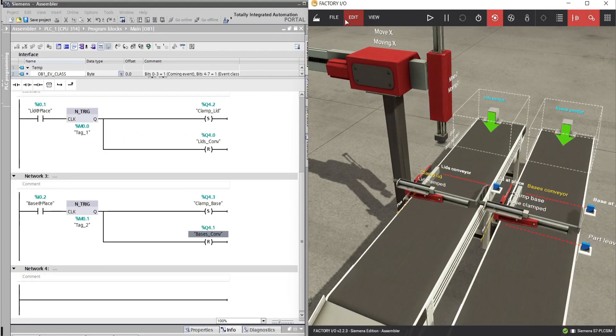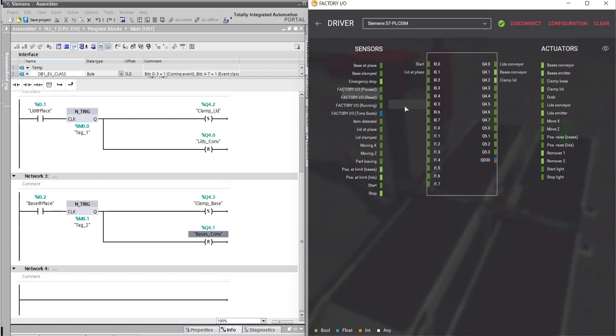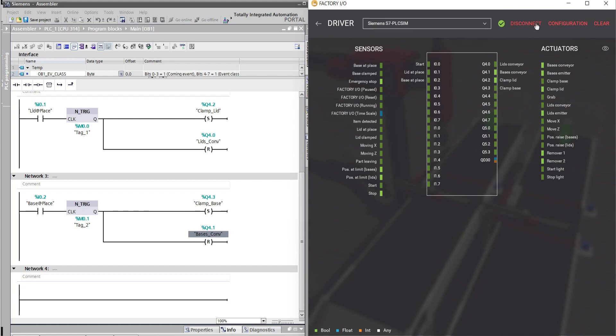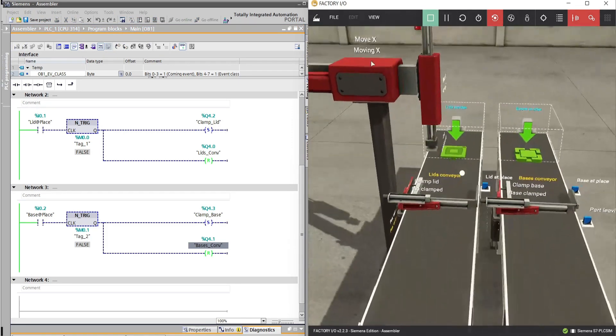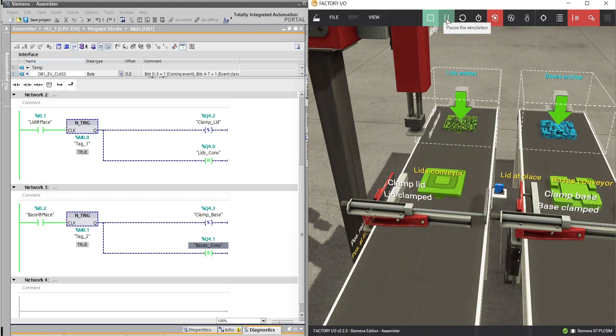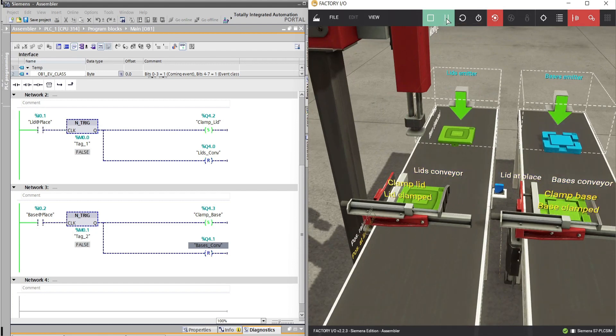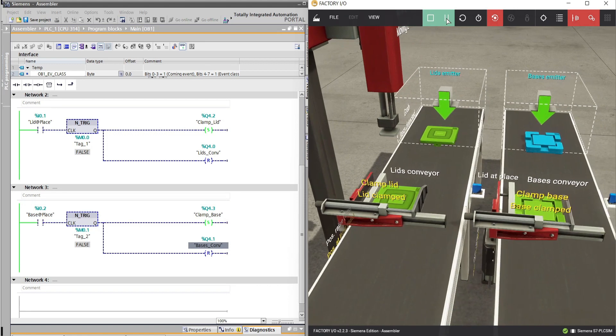Let's test the program again. Don't forget to add new instructions or addresses in the Factory IO PLC configuration. Add clamp base for output Q4.3, and base at place for input I0.2. As you can see, the lid at place and base at place sensors will energize and de-energize when products pass the sensors, and both conveyors stop as the clamps catch the products.